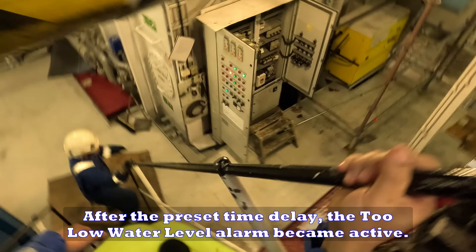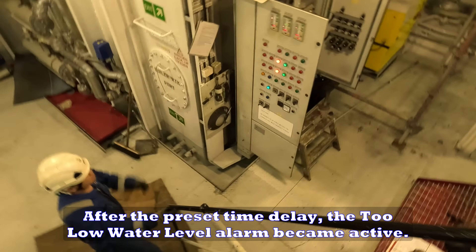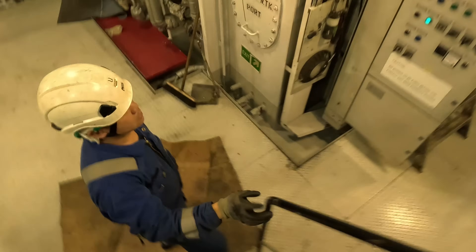After the preset time delay, the Too Low water level alarm became active. This mimics the actual condition where water level drops too low, causing the magnetic level switch to open its normally closed contact.